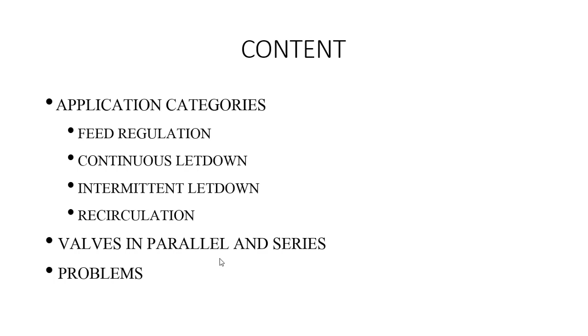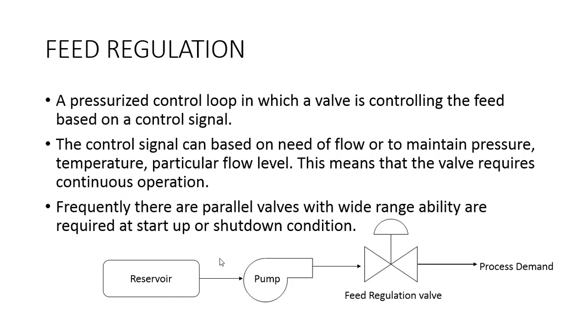This means that the valve requires continuous operation. Frequently, parallel valves with wide rangeabilities are required at startup or shutdown conditions. At startup, the flow rate is low while inlet pressure is high due to the pump. Hence, the pressure drop across the valve is very high, which requires a special trim, probably anti-cavitation, to handle such process conditions. At full load, the flow rate is high but the pressure drop across the valve is low, due to which the required Cv is very high. To meet both startup and full load conditions, a good valve with wide rangeability is required.